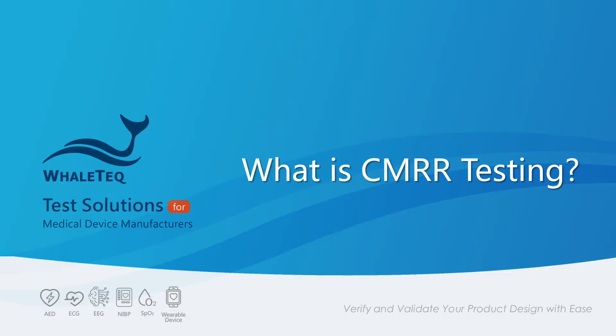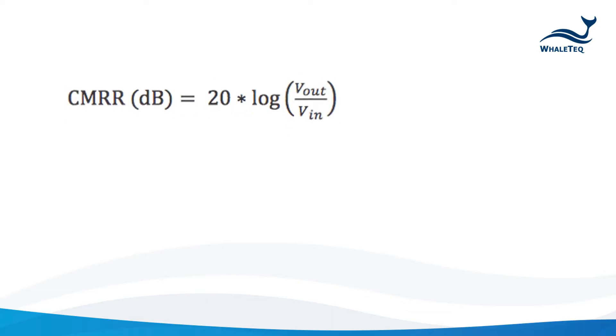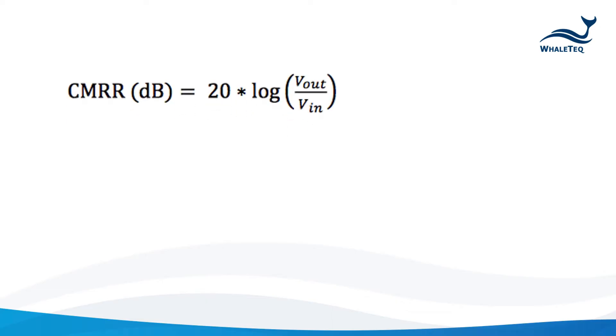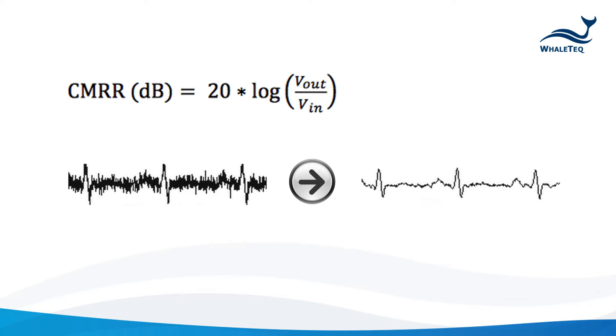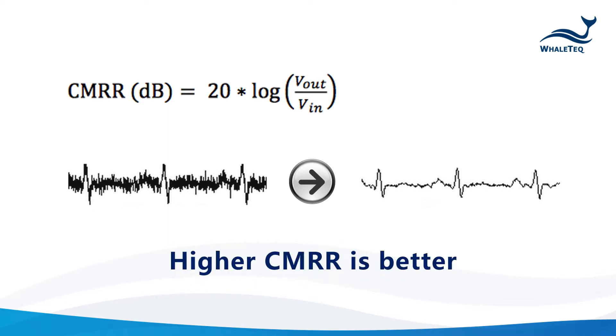What is CMRR testing? Common mode rejection ratio, or CMRR, is the ratio of differential gain to the common mode gain, usually measured in decibels. In simpler terms, CMRR measures how severe of an electrical noise condition a device can withstand.